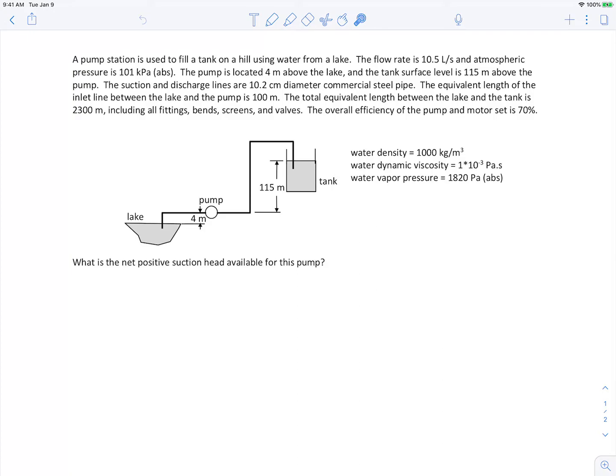The question asks for the net positive suction head available, or NPSHA, for this pump. The NPSHA is a pipe system property — it's not a pump property, so it won't have anything to do with the pump itself. To find it, we're going to apply the extended Bernoulli equation from point 1 at the lake surface all the way to point 2 on the suction side of the pump.